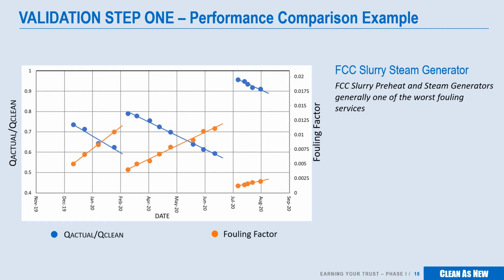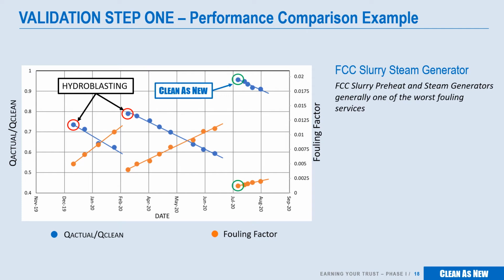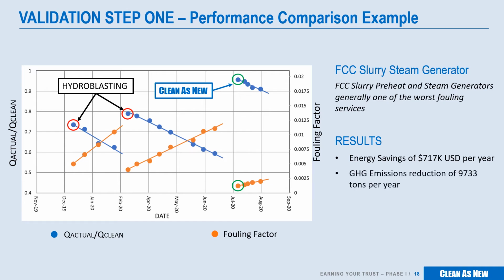The data shows these bundles were previously cleaned to 73 and 79% by hydroblasting. Clean as New was able to return these bundles to 97% in less than half the time normally required for hydroblasting. The calculated dollar impact of better cleaning in this case is over $700,000 per year, with an estimated greenhouse gas reduction of 9,733 tons of CO2 equivalent.